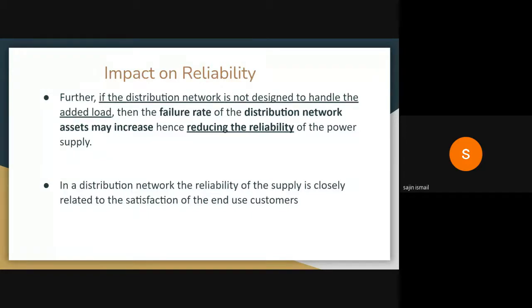But at home, we might not even know a charging point exists there, and the distribution utility might not know either. So the failure rate of distribution network assets may substantially increase. The transformer gets heavily overloaded, and the utility may not understand where the load is coming from. It suddenly increases from one day onwards, and only after a transformer failure do we find out. This has a huge impact on reliability.